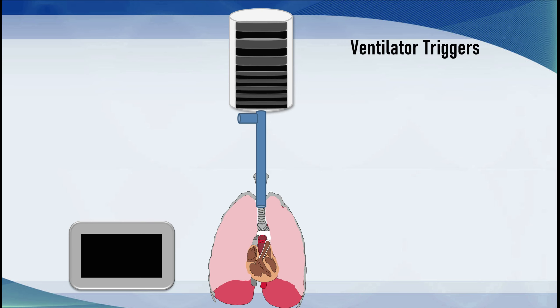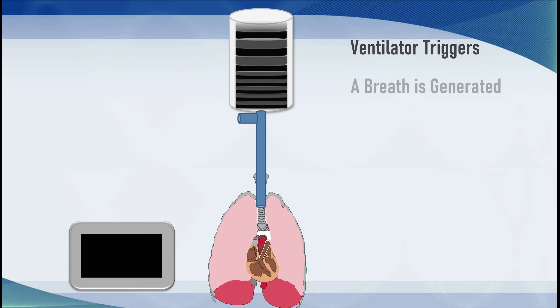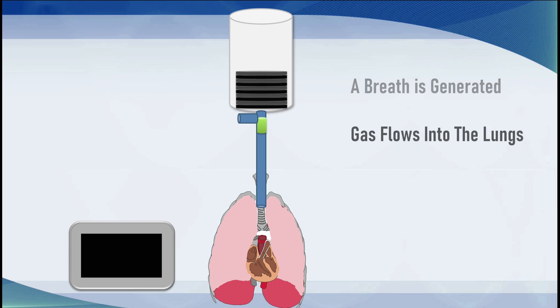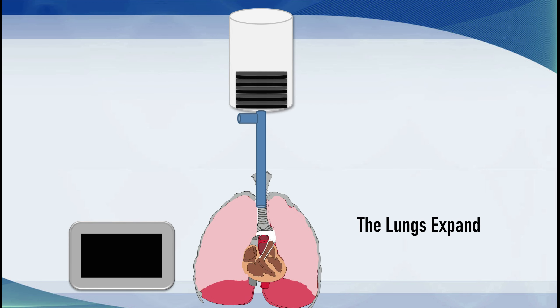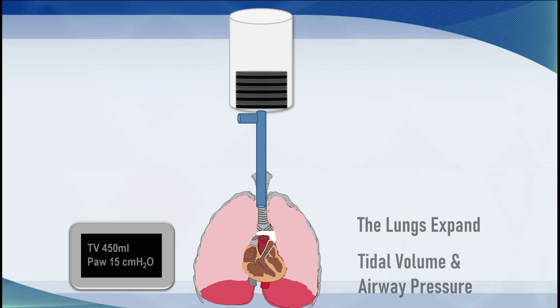The ventilator triggers — and we'll talk in an entire tutorial about how ventilators trigger — and a breath is generated. That may be a volume control breath, a pressure control breath, or a completely unsupported breath. Gas flows into the lungs and that flow is always positive, so there's a flow waveform that can be generated. The lungs then expand and the tidal volume and airway pressure are measured. In this case, the tidal volume is 450 mils and the airway pressure is 15 centimetres of water.